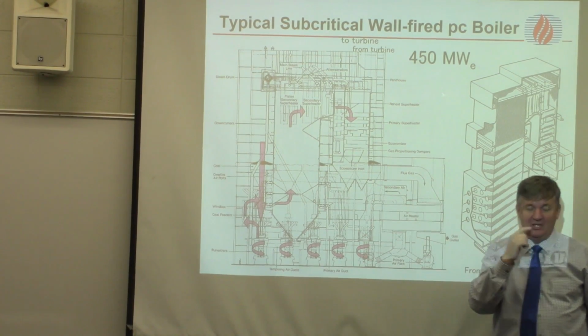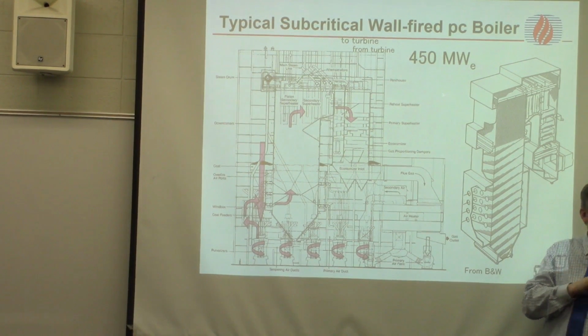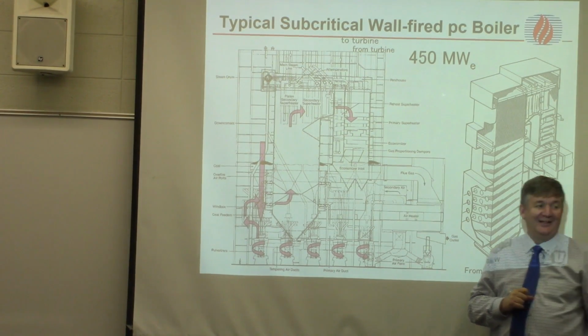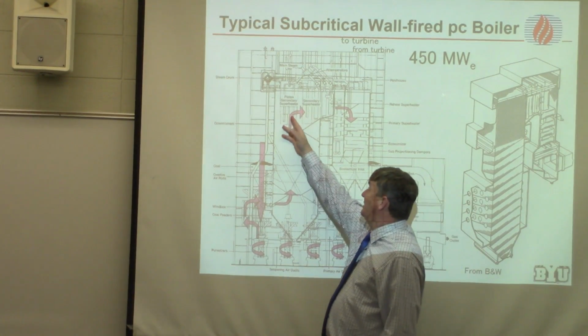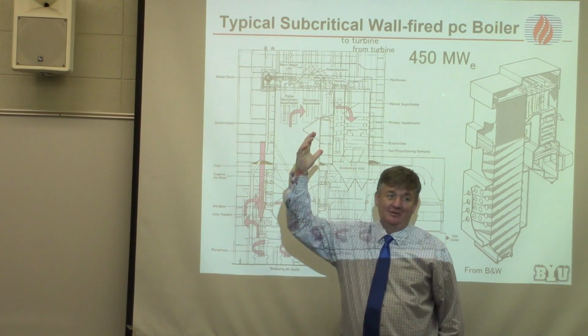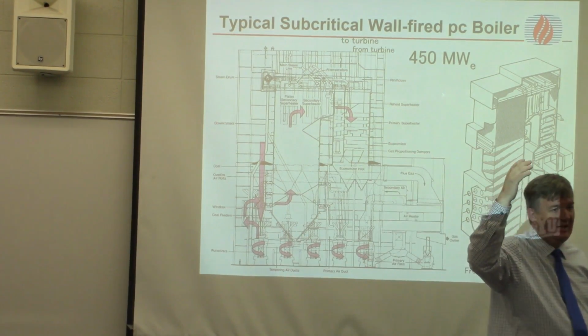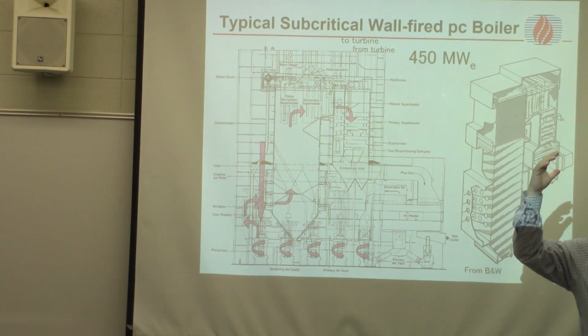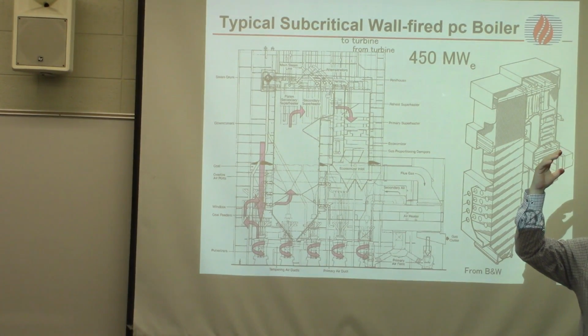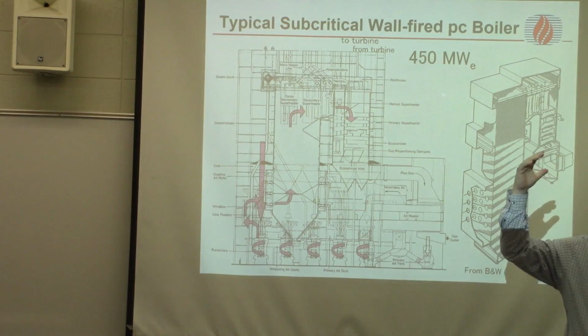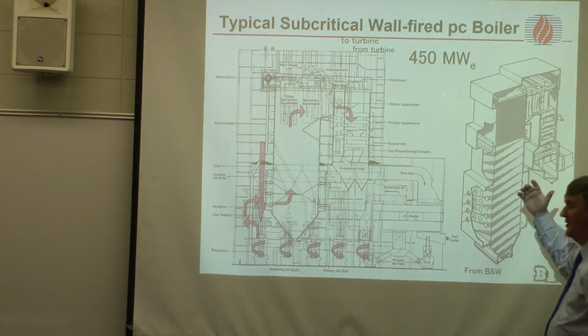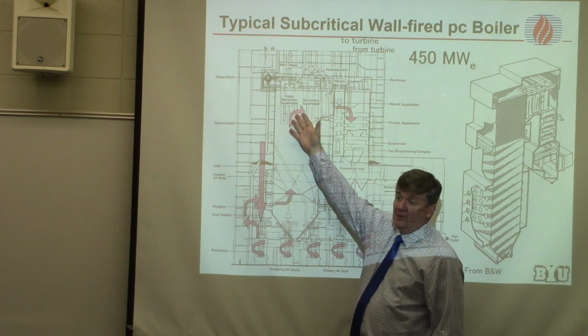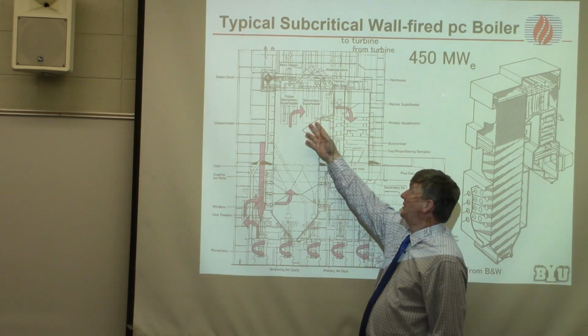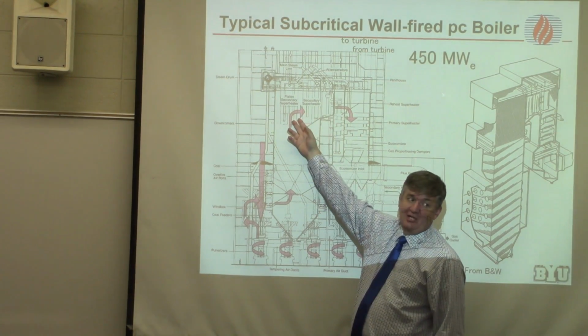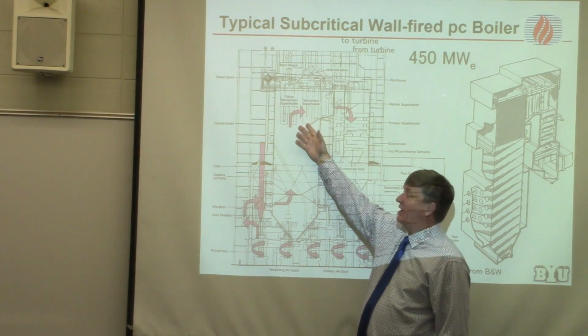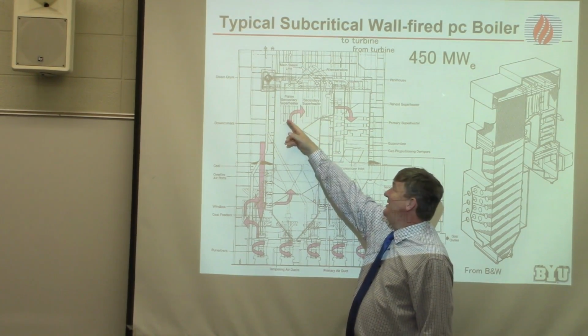We'll talk later this week and next week about nuclear power plants, but one of their features is they never superheat the steam. But in coal-fired power plants they do. So they'll heat the steam up to about 600 degrees C. Anybody know what the critical temperature of water is? You remember that number? It's about 370 degrees C. This is well above the critical temperature, but it's not necessarily above the critical pressure. This particular boiler is not above the critical pressure, but some of them are.